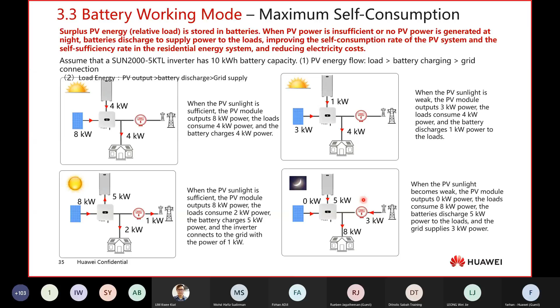And then this one is for during the night. During the night, your house load is maybe 8 kilowatt only during that time. Then your Luna just needs to be able to give you 5 kilowatt only, because that is the maximum. You remember the setting that I showed you before, right? The maximum the Luna can discharge is only 5 kilowatt. So the remaining 3 will be taken from the grid.